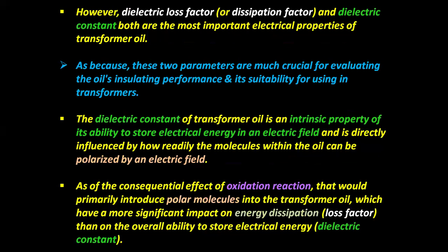However, dielectric loss factor or dissipation factor and dielectric constant are both the most important electrical properties of transformer oil, because these two parameters are crucial for evaluating the oil's insulating performance and its suitability for use in transformers.